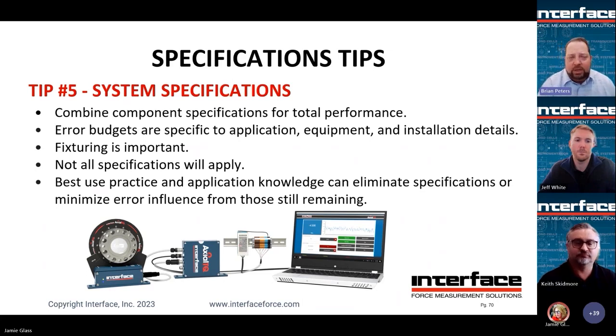So always follow best practices, because if you want to get the performance that is specified on a data sheet, you have to make sure you're hooking up to the load cell correctly and utilizing it in the proper manner. We talked about it before, not all specifications will apply, but through best practice and also understanding from an application standpoint, you can really eliminate most of the specifications on a data sheet, and you're going to be left with three or four maybe that are of importance when you're looking to select a sensor for testing.